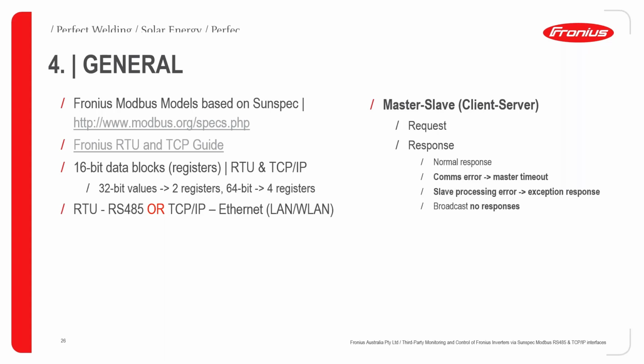The key point to take away there is that in terms of implementation, we implement 16-bit holding registers in terms of predefined data blocks, which you'll see later. Some registers can have bigger values, so maybe 32-bit, 64-bit, and so on, which means you need to read multiple registers.